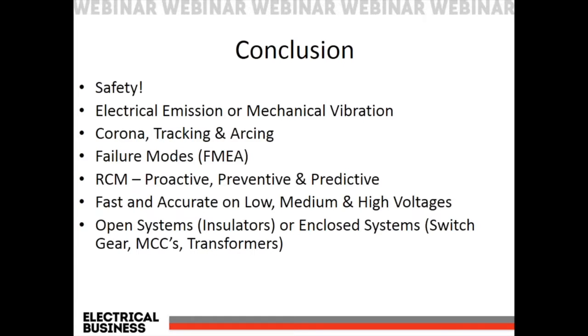But what I will mention is that, again, infrared will not see corona. And infrared will not be able to tell you by looking at a hot spot, maybe we're seeing a hot insulator, or that heat is obviously a different temperature change than the rest of the electrical assets, but it doesn't tell you if it's tracking or arcing. But what we can do is confirm that what we're hearing is corona, tracking or arcing based on our spectral analysis and sound analysis through ultrasound.